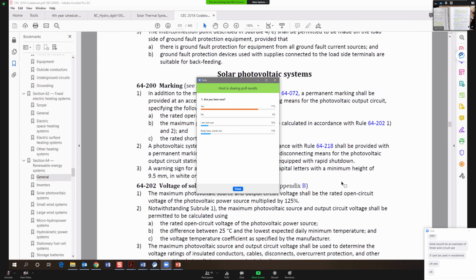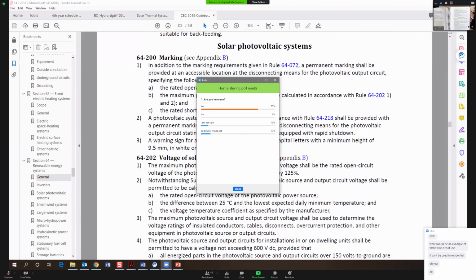Okay, so that rule, sub-rule 1, item B, tells you the maximum circuit voltage is calculated according to 64-202, 1 and 2. So 1 is: maximum photovoltaic source and output circuit voltage shall be the rated open circuit voltage of the power source multiplied by 125%. So we know the open circuit voltage is the maximum voltage a panel can output, right? But here, you calculate the voltage as the maximum source open circuit voltage multiplied by 125%.